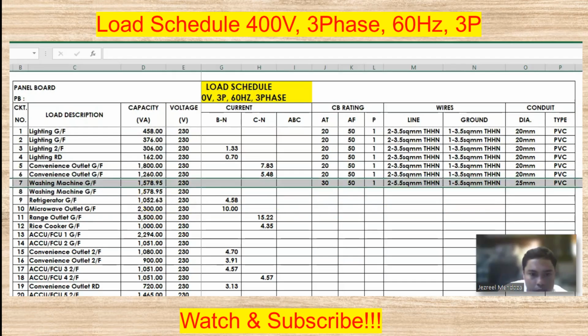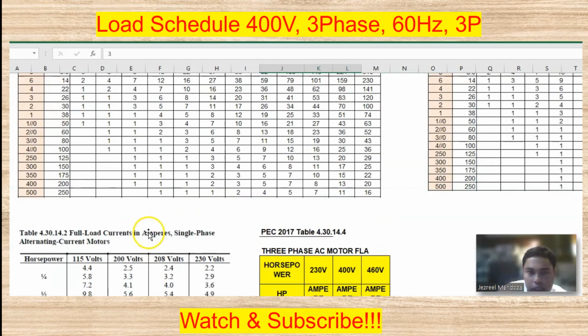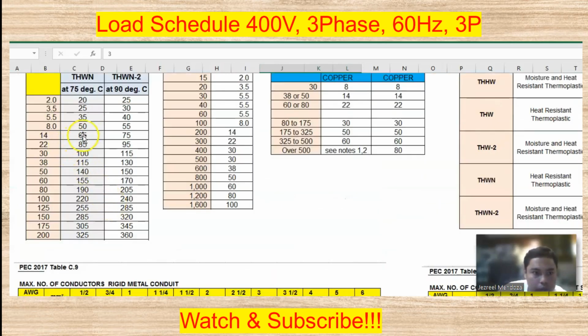So if you look to the PEC table, itong 5.5 square mm, it can withstand up to 35 amperes at 75 degrees Celsius.